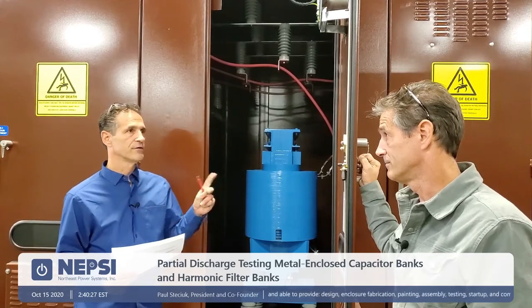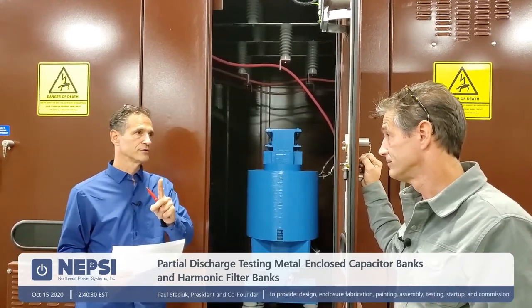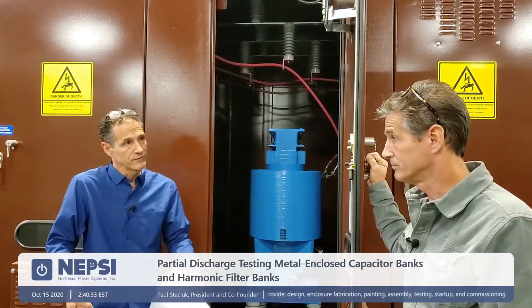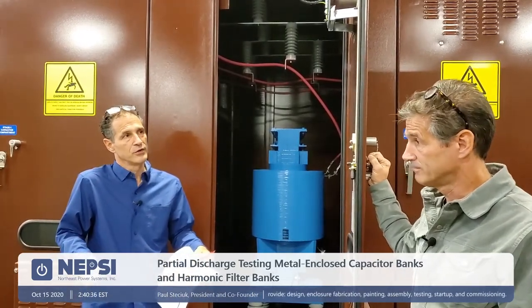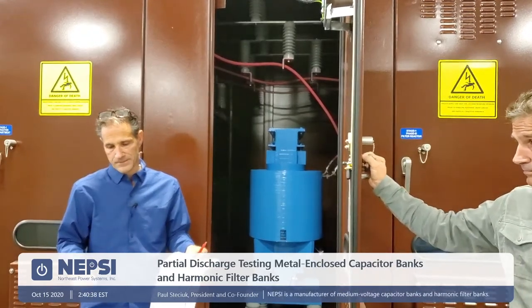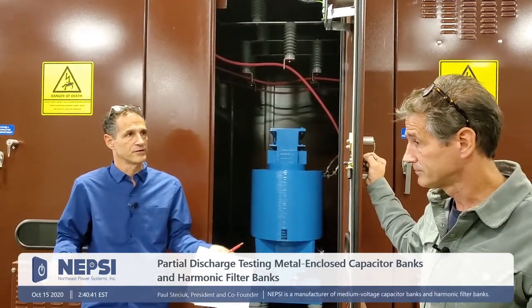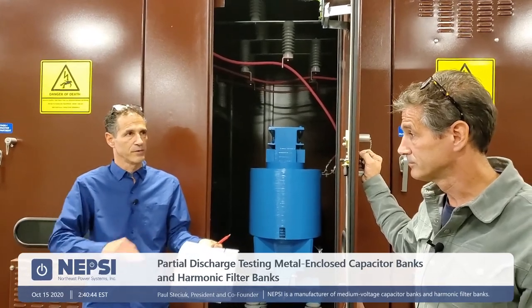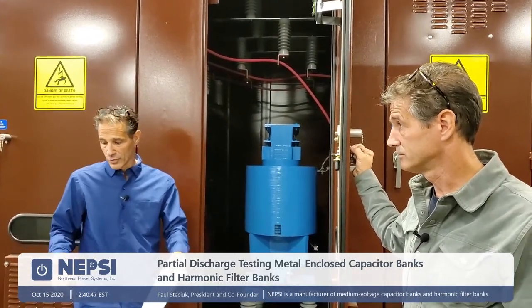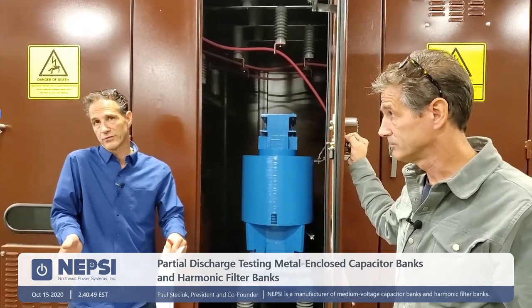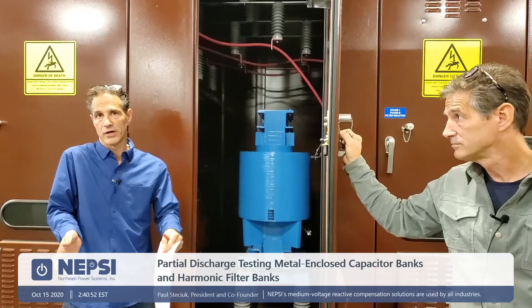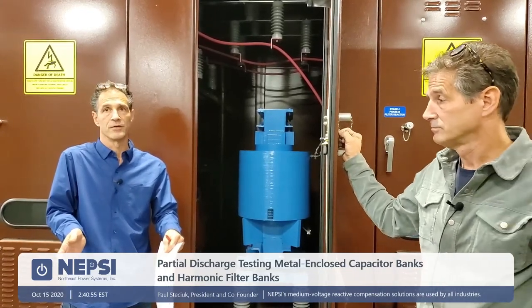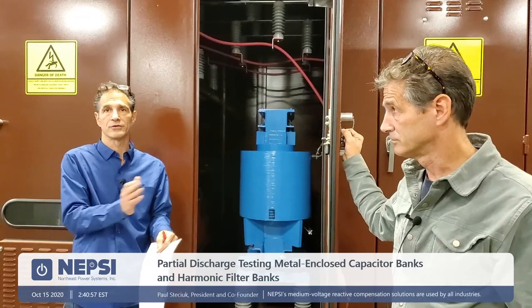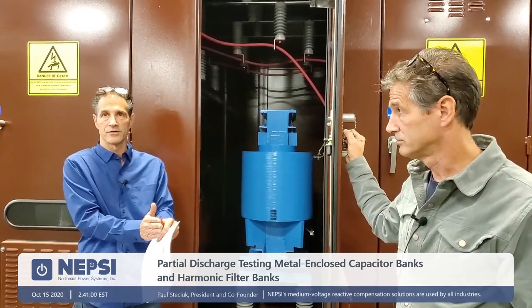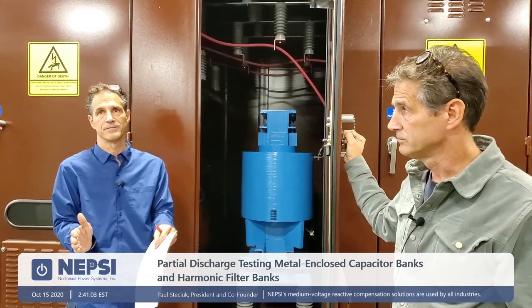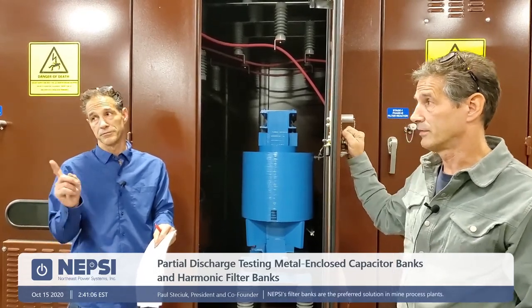There was one other thing I remember on one of the previous projects: the breakers come with a lifting bracket. Correct. And we had two identical pieces of equipment. On one, the brackets were removed because the assembler remembered to do so, and we passed partial discharge right away. On another, one of the brackets was left on by mistake. That bracket was causing a clearance issue, but not a significant one. What we noticed is that the partial discharge test between one system and an identical one was completely different. It passed impulse with the bracket in. Correct. But it didn't pass partial discharge.